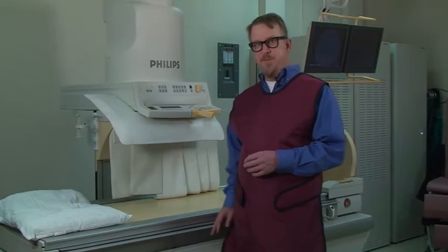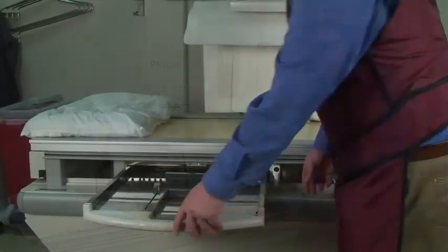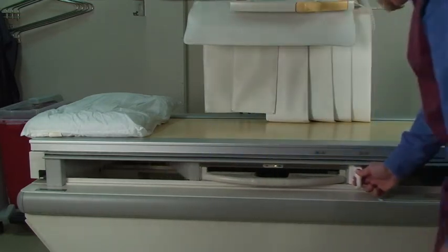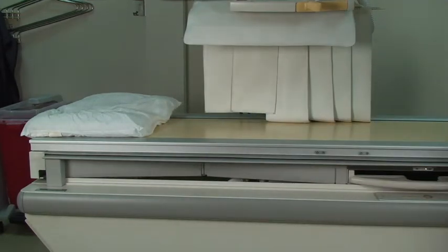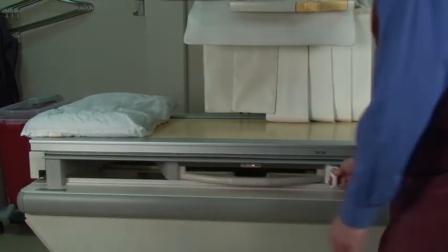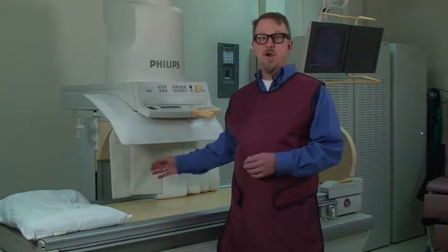The table contains a bucky tray to hold a cassette for a single image. When the fluoroscopy unit is used, the tray is moved to the patient's feet so that the opening in the side of the table is shielded by the tray's slot cover, which contains at least 0.25 millimeters of lead equivalent. A curtain of at least 0.25 millimeters lead equivalent should be connected to the tower when the table is positioned horizontally. If the X-ray tube is above the patient, then corresponding safety precautions should be taken to satisfy recommendations made in NCRP Report number 102.